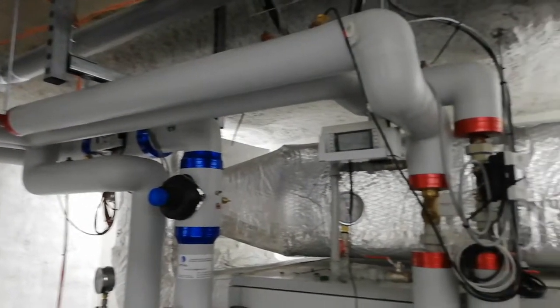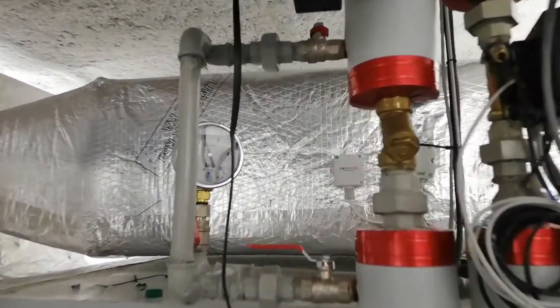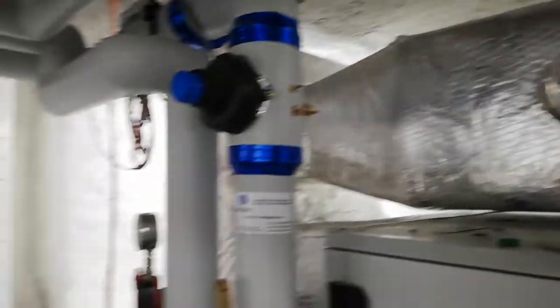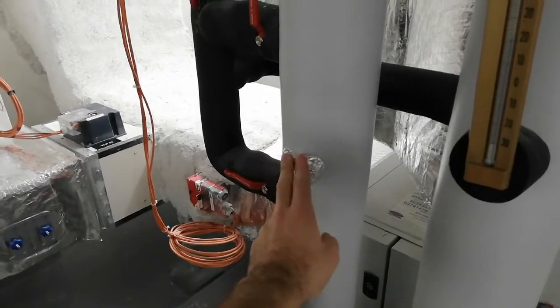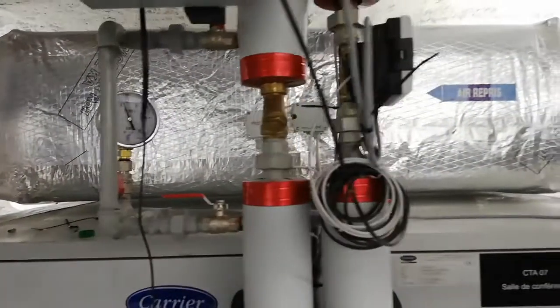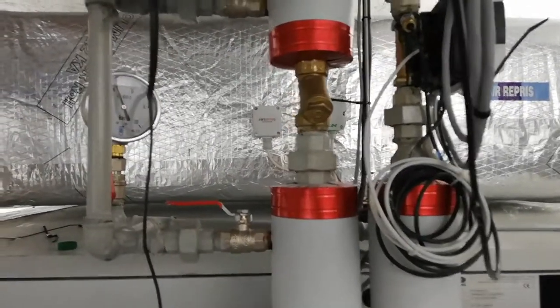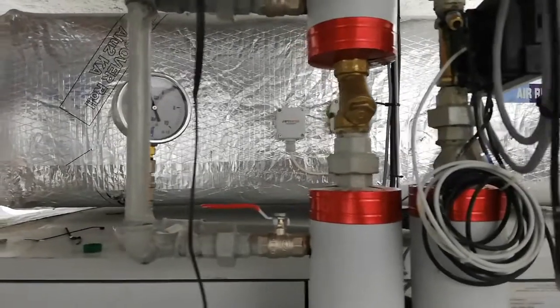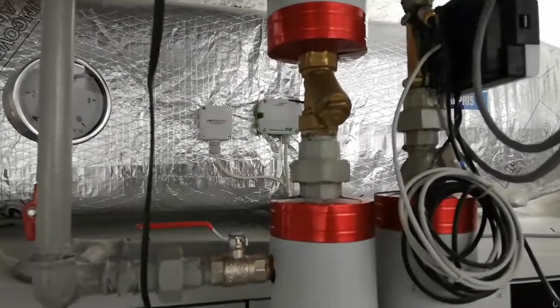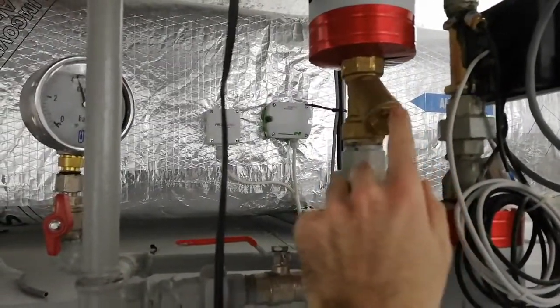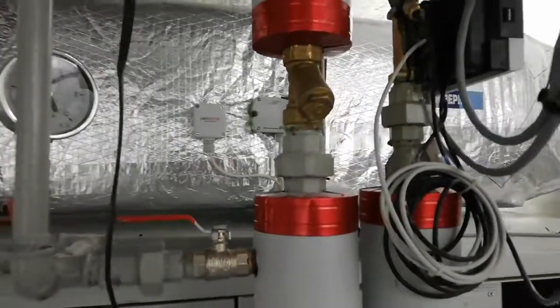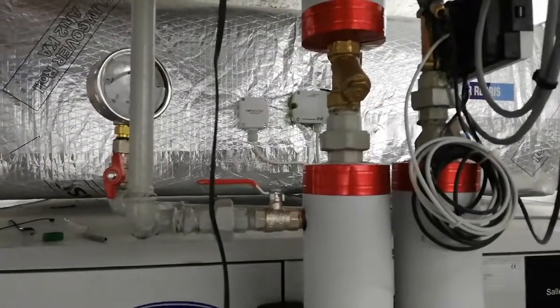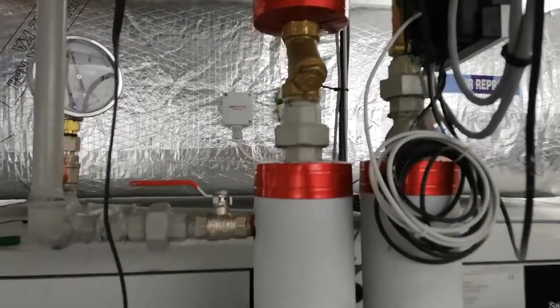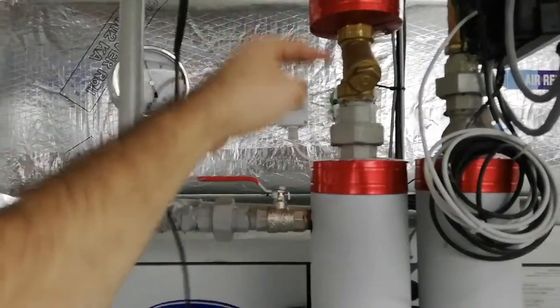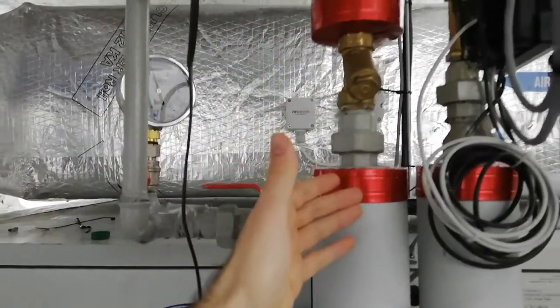The second component you will have to install is the strainer. Here you have the strainer for the hot water coil, and here you have the strainer for the chill water loop. It's insulated so you don't see it well. With the strainer you will make sure that your water system remains clean all the time. All the impurities will be captured by this strainer using a small filter, and they will remain in this small location. What's very important is to always monitor the pressure drop in your strainer, because as the impurities flow in, they will build up and the pressure drop through the strainer will increase a lot.